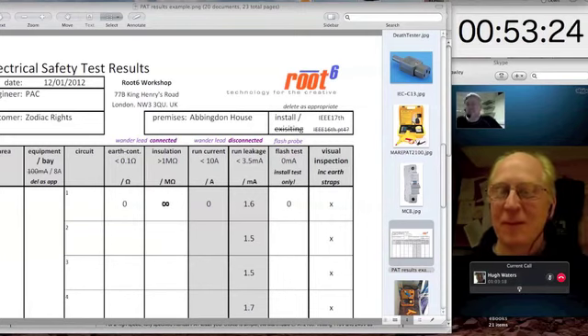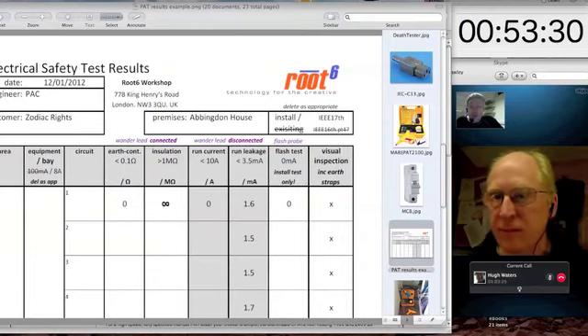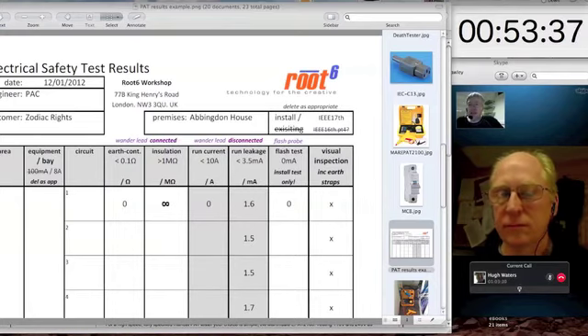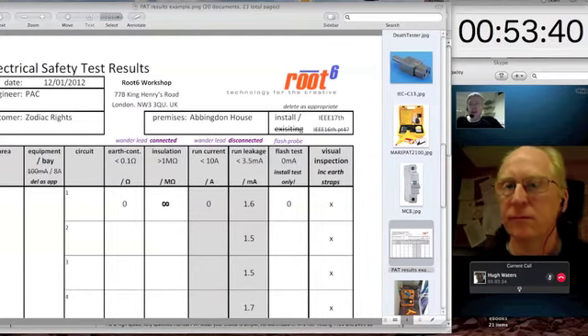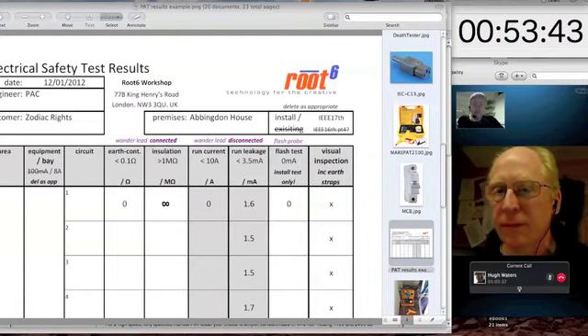So the next test that the machine does is what it calls an insulation test, and we're looking for more than a mega ohm, more than 1 million ohms of insulation impedance. And what that does is it takes a 500 volt DC voltage and it applies that between the live and the neutral conductors shorted together and the earth to make sure that there's no breakdown in earth insulation. To make sure that within the piece of equipment or within the cabinet there are no points where a live conductor is so close to an earth that it could arc across. So that's the insulation test, and what we're looking for there is greater than a mega ohm, and in fact, ideally, we're looking for infinity. We're looking for an impedance that's too large to be measurable because it's going through air. Yeah.